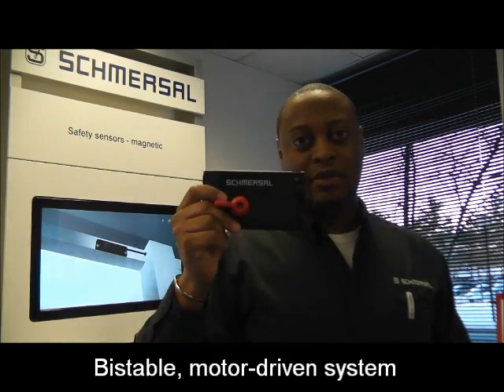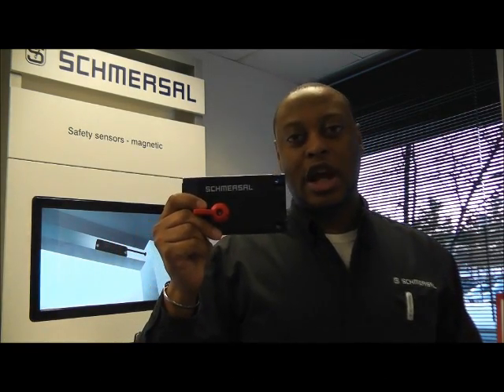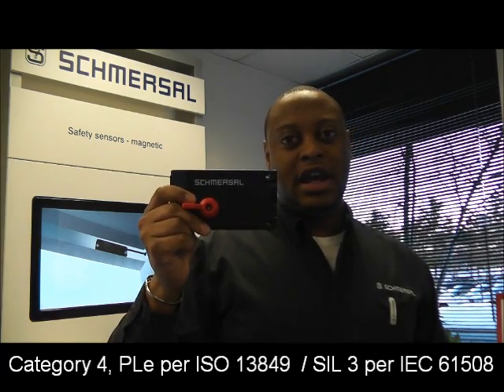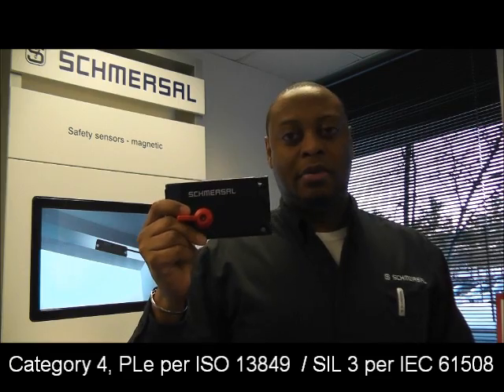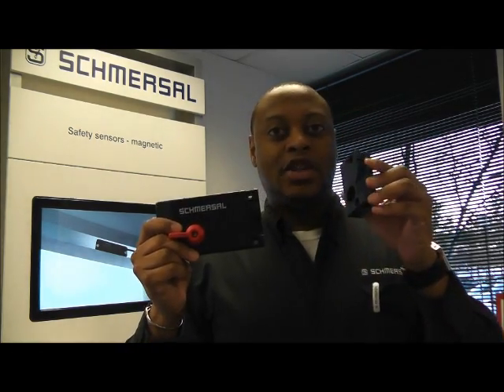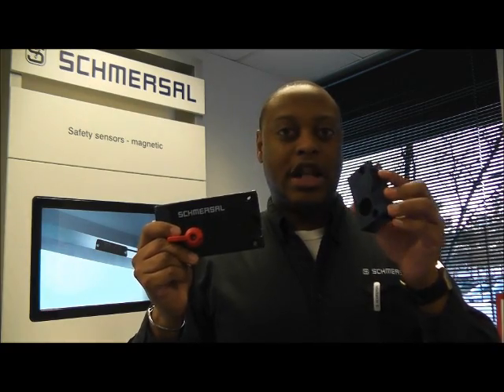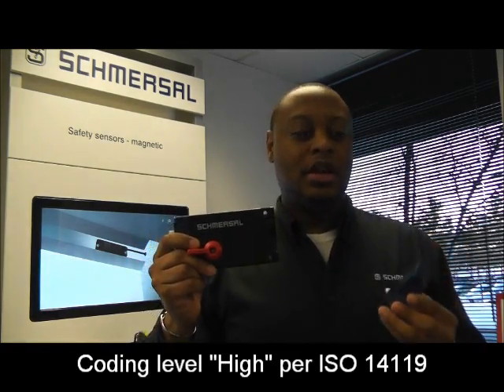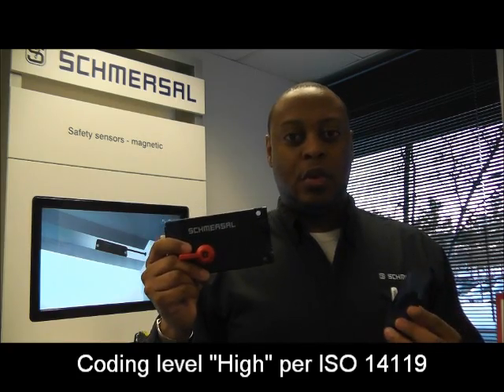This Schmersal electronic device is capable of achieving Category 4, Performance Level E per ISO 13849, as well as SIL Level 3 per IEC 61508. The I1 and I2 options for an individually coded actuator allow it to be used in a high-level coding application per ISO 14119.